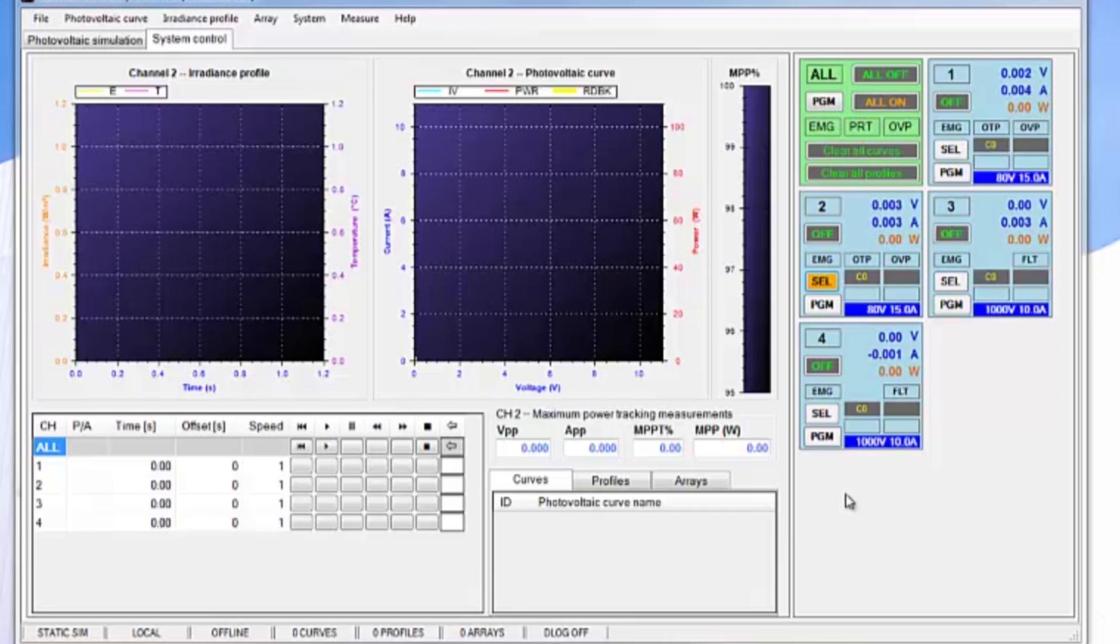Channels 1 and 2 are 80V 15A PV simulators. Channels 3 and 4 are 1000V 10A PV simulators. The TerraSAS software can recognize and control up to 48 channels.